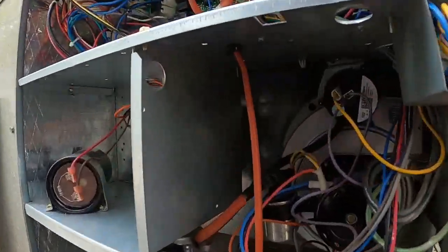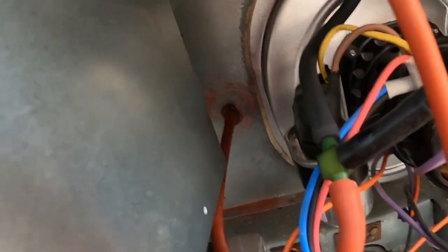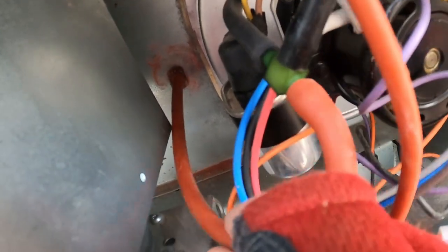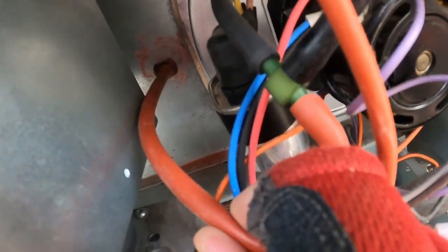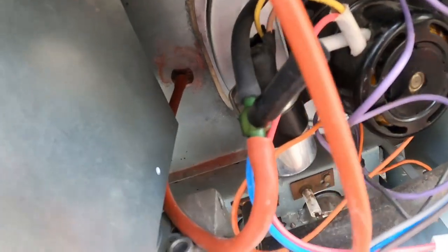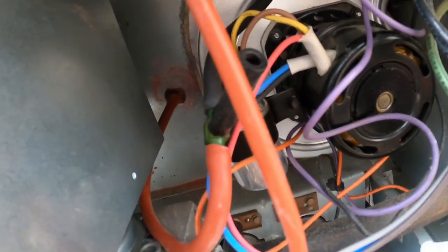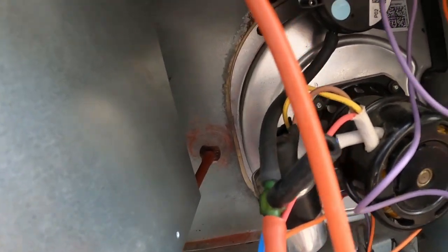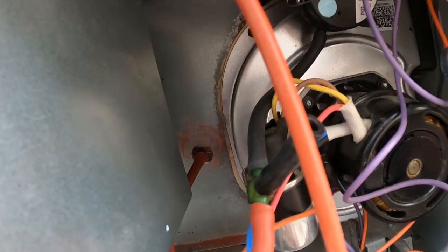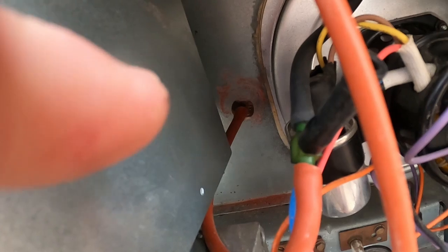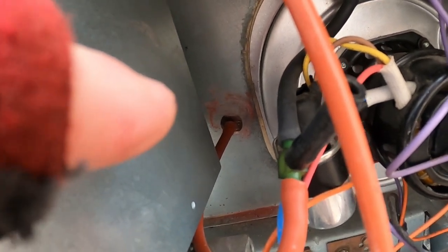Let's see what I'm doing. This is my hose port back there in the back, which I can already see this model Trane. If you look back there and watch that thing, see it wiggling? See it spinning? Bad design from Trane on anything since I think 2015 or 16. I think we did this on an inducer motor change one time. All the new package units got away from it, they quit putting the hose port back there because it would rust and corrode and come apart.